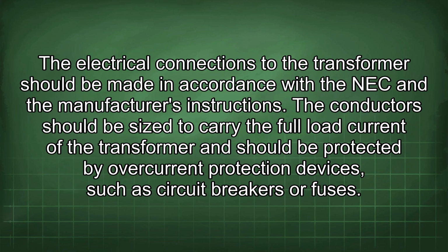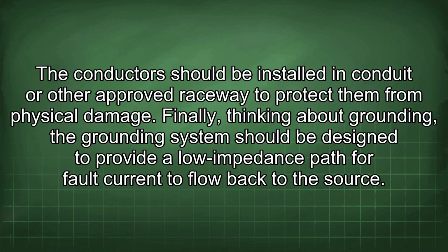The electrical connections to the transformer should be made in accordance with the NEC and the manufacturer's instructions. The conductors should be sized to carry the full load current of the transformer and should be protected by overcurrent protection devices such as circuit breakers or fuses. The conductors should be installed in conduit or other approved raceway to protect them from physical damage.